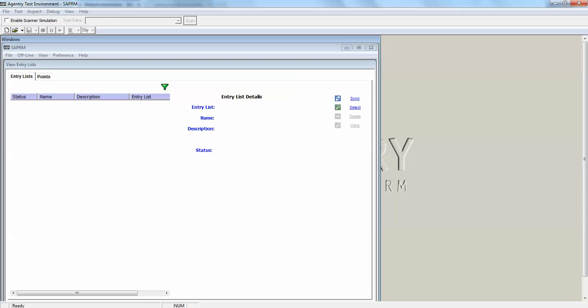Or then I could also be able to see what is going to happen in the next few hours or next few days. This time dimension is always from the last failure of the equipment. So we have a very well-known terminology around this dimension, the mean time between failure. So say an equipment has been reported to be broken down via notifications or work orders, etc. three times in the past history as 3,000, 7,000, and 5,000. So the summation of that is 15,000 and divided by 3 is 5,000.